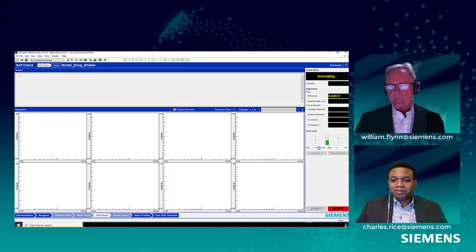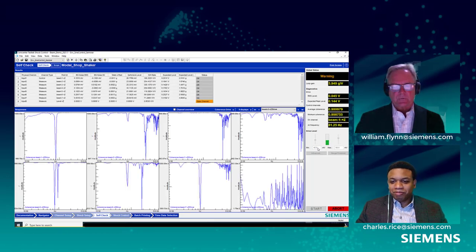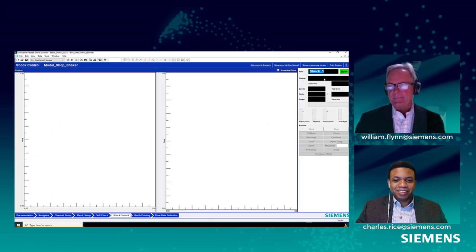I had a pretty high minimum here for some reason. I probably could have turned that down, and the self-check wouldn't have taken as long. However, we'll continue on. We finished it, and I got good coherence, 0.99999. Not as good as it gets, but pretty much. I'll take it.